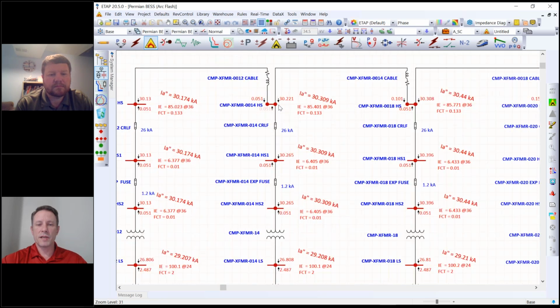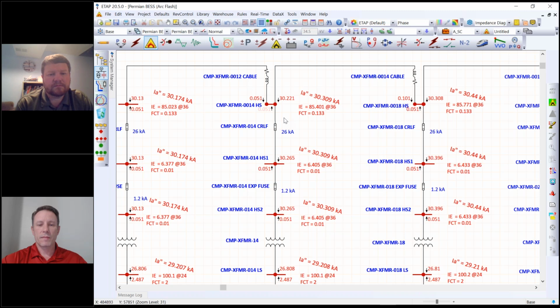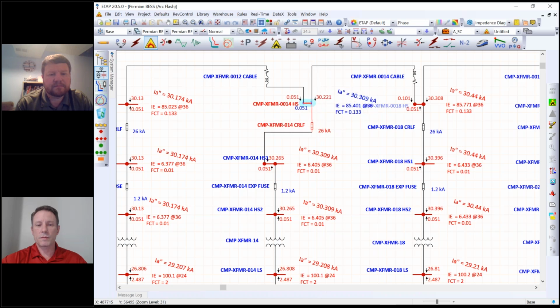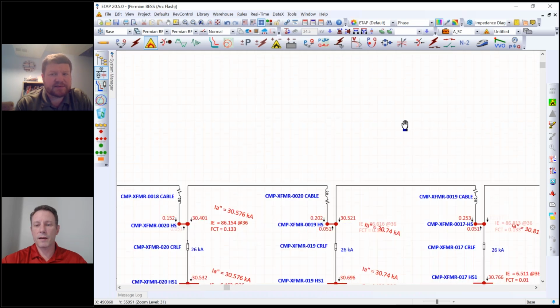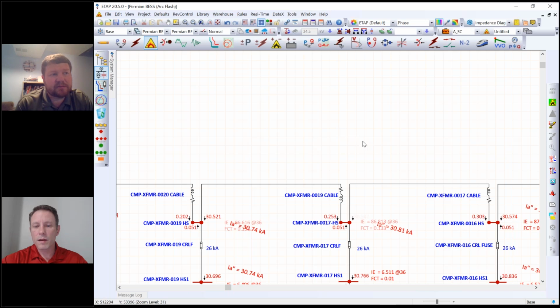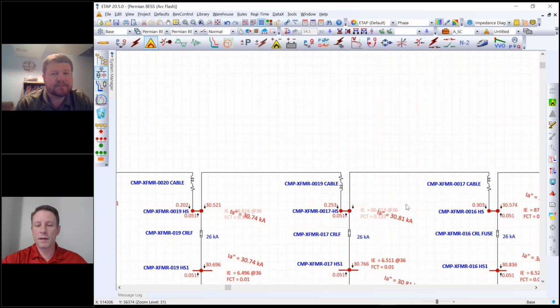So at the high voltage, the arc flash is actually worse than I expected it to be. This is about 85 cals here. Likely, note that that's the Lee method, so generally it's going to be a very conservative result, right? It would be much less than that.